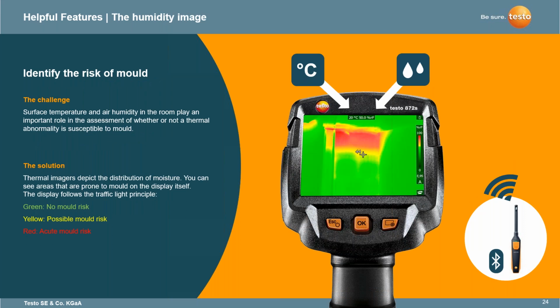Here's an example of the humidity image and humidity feature within one of the imagers, the Testo 872S. The challenge: surface temperature and air humidity in the room play an important role in assessing whether a thermal abnormality is suspect for mold. The solution: the thermal imagers depict the distribution of moisture, so you can see the areas prone to mold on the display itself — the red, green, and yellow.